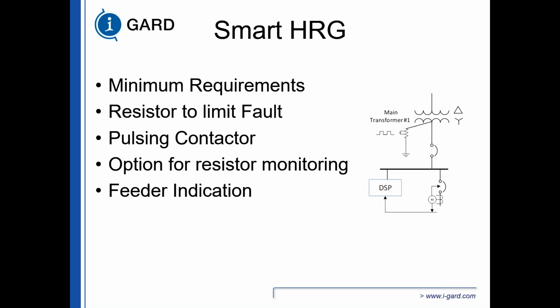Feeder indication. You should have the ability to determine where the fault is in your system at a glance. For example, the fault is in feeder number 5 in this system right here. So right away, you start looking for your fault at the location where it's safe to look, rather than the standard HRG system that says you have a fault, the fault is gone, you have a fault, the fault is gone. Now you can have a system that says you have a fault on feeder number 5. Initiate the pulsing and then start looking for that fault from feeder number 5 down, because you've already got a starting point of where to find it. So it's easier to find the fault.